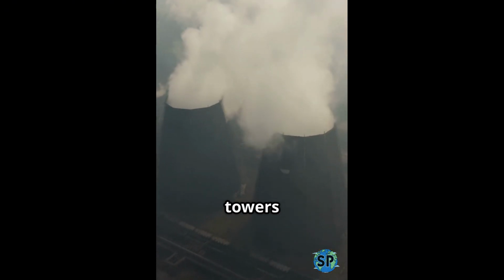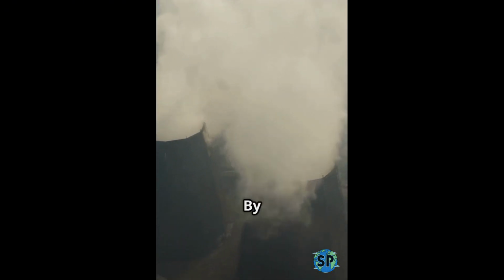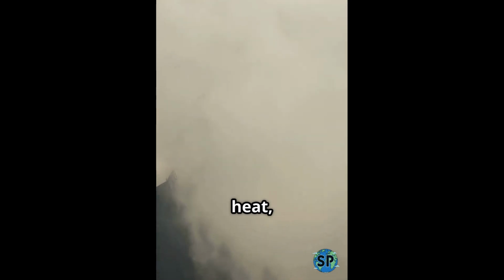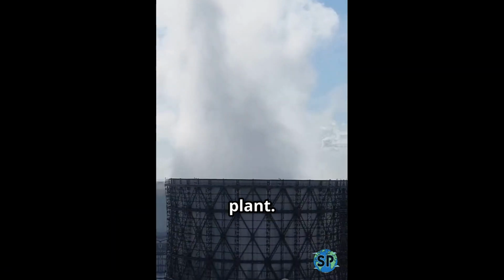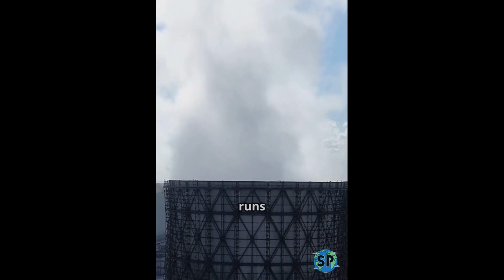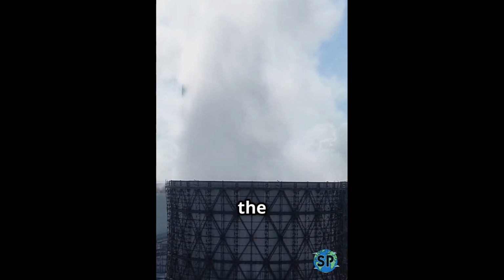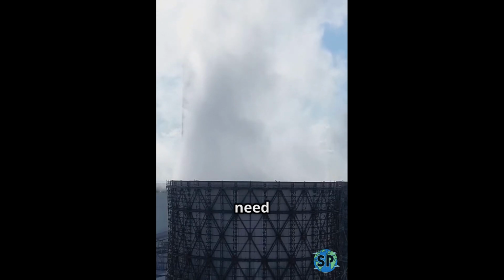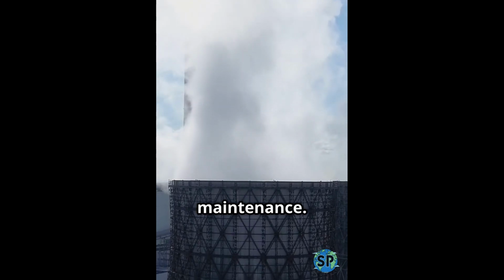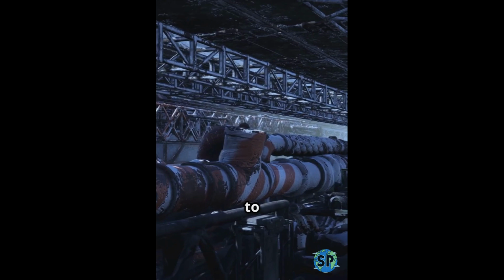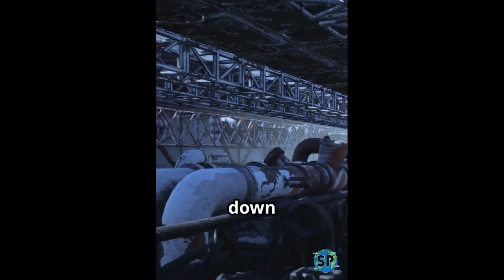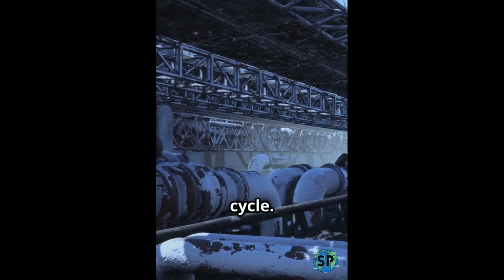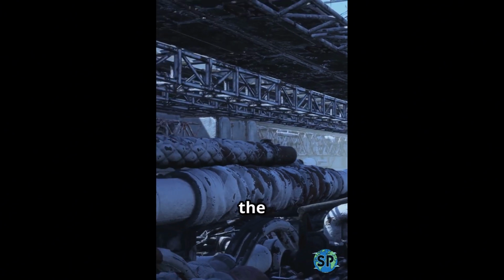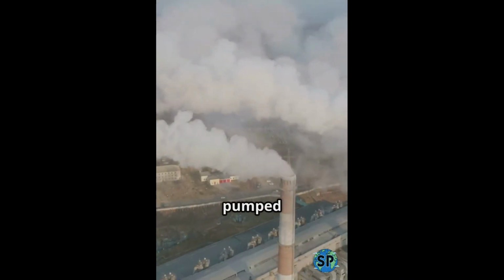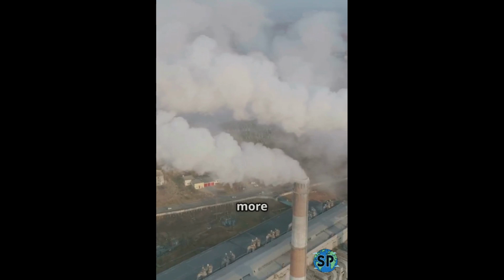The cooling towers play a vital role in this system. By efficiently removing excess heat, they help to maintain the optimal operating conditions for the plant. This not only ensures the plant runs efficiently, but also extends the lifespan of the equipment, reducing the need for costly repairs and maintenance. The process of moving hot water to the top of the tower and spraying it down is a continuous cycle. The water is collected at the bottom, cooled, and then pumped back into the system to absorb more heat.